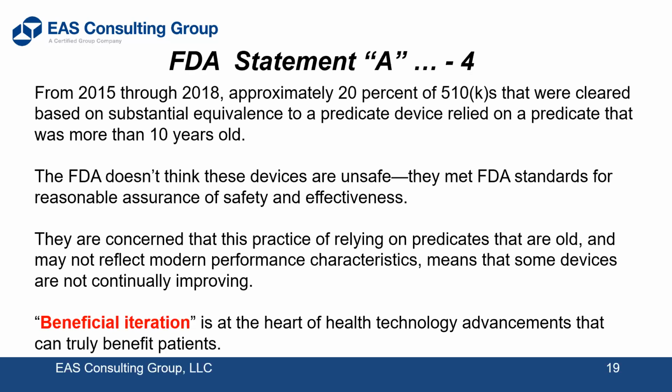But the purpose of the center's desire and the FDA commissioner's desire, now we do have a new commissioner now, but as far as I know, that hasn't changed what we're presenting here, is beneficial iteration. That's kind of quite interesting. So when you talk about substantial equivalence, you put an asterisk on it, and the asterisk leads you to beneficial iteration. In other words, slight improvements, still under the 510K arrangement, that improve the product in terms of its effect on the situations dealing with the patient.